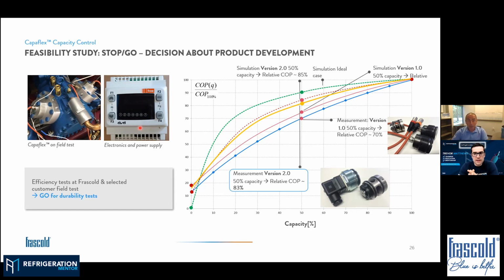No, I wasn't mentioning it, but you are right, this is what we did. We had to optimize the pressure drop through the valve, for example. And another thing that's been optimized in these versions is the sealing between the high pressure and low pressure, because the pressure difference is crazy in the CO2 application. Trying to do a sealing with an O-ring isn't the easiest thing anymore. So these were the two main improvements we made.